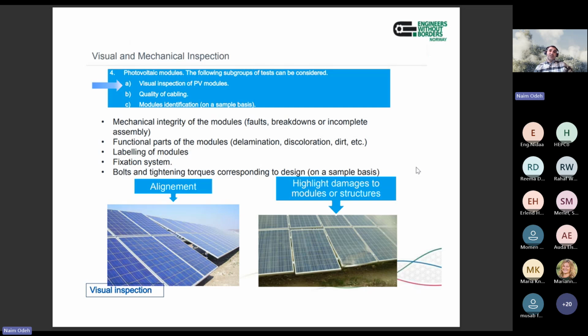In addition to checking these points, for most projects, and to make operation and maintenance easier, most O&M organizations now recommend having the modules tagged. Usually we have cables tagged, inverters tagged, the main equipment, but now some recommend having labels for modules too, giving each module a number. For small projects this is an easy job, but it's a challenge for big, mega-scale projects where you need to label all solar modules.